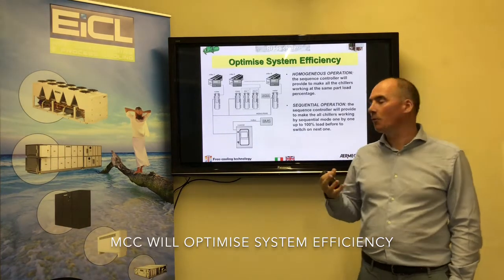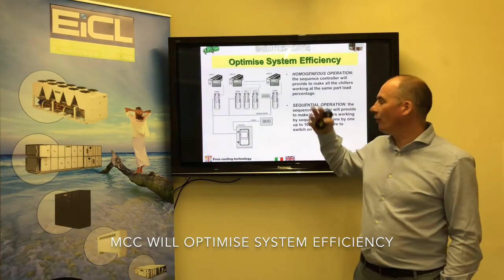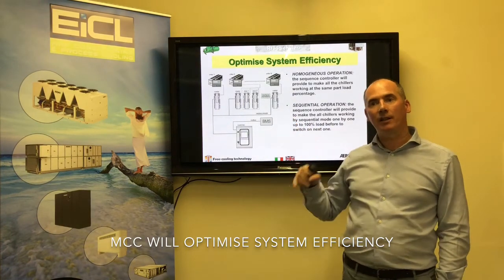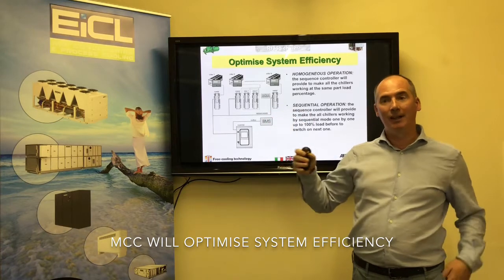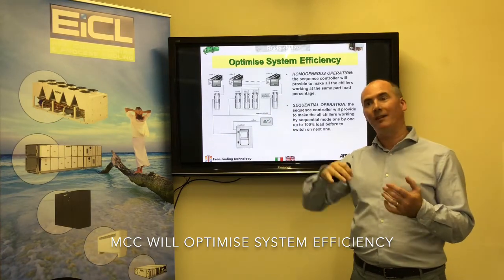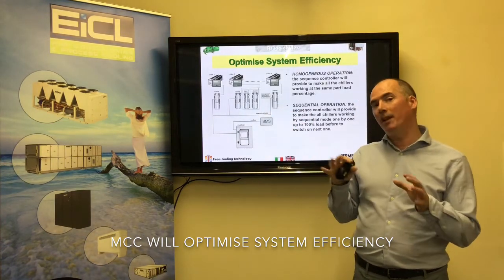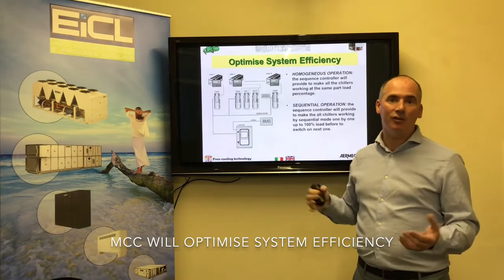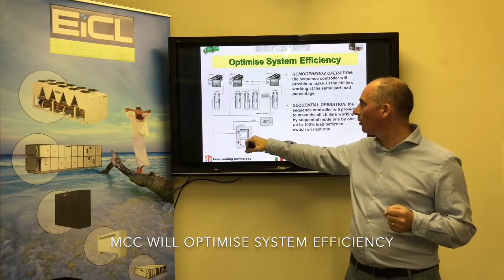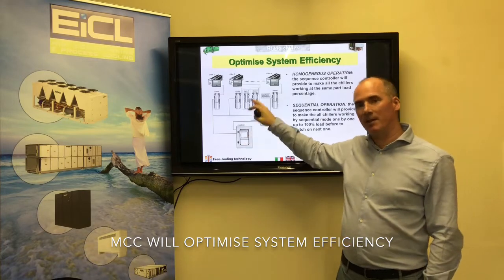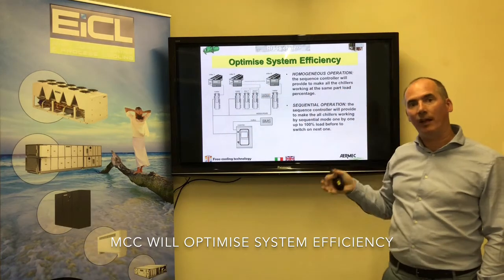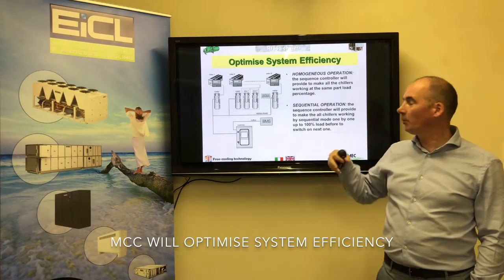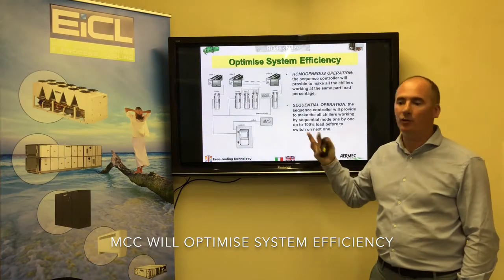So AERMEC designed what was called the MultiChiller sequence controller, and unlike the BMS historically giving an enable signal to each chiller, and like I said, it would run one, then if it needs the other, it would run that, but it wouldn't be anywhere near as intelligent as the MultiChiller sequence controller. This is programmed specifically to suit the type of chillers and the type of compressors in the chillers. So whether it be a scroll, inverter screw, non-inverter screw, and so on.